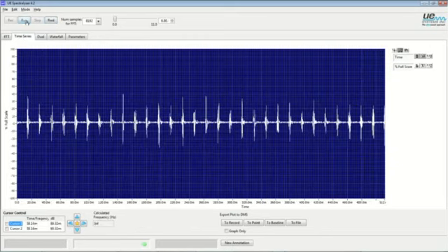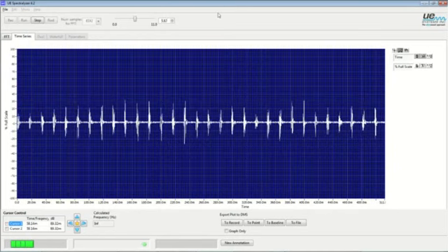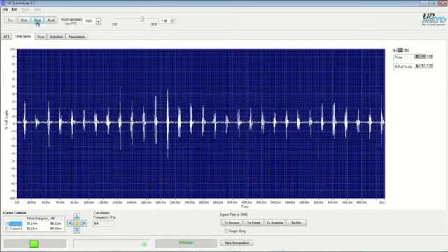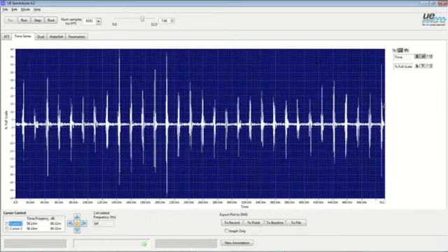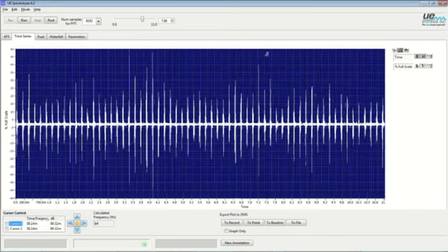Going back to here, if I rewind the recording and run it, we can see that we have some uniformity in the timing. But we're also seeing some changes. If I look at the whole recording here, we see some variations in this amplitude. That's the same signature as tracking that would not be present in a purely nuisance corona event. As I zoom in, that becomes even more clear.